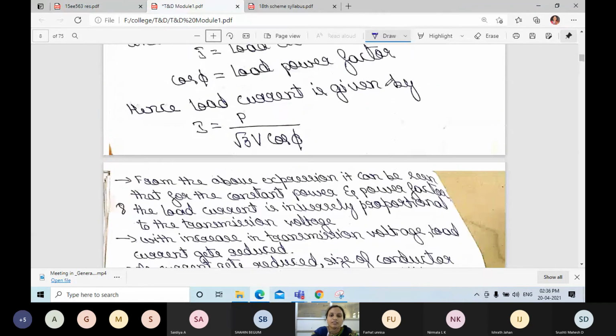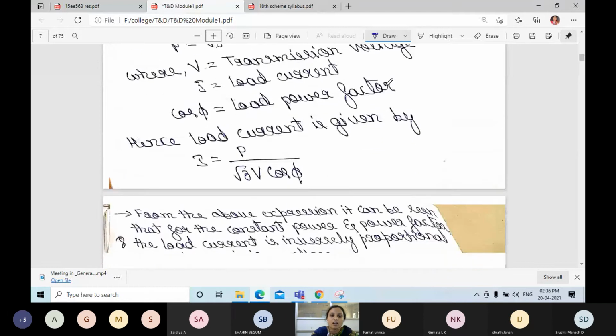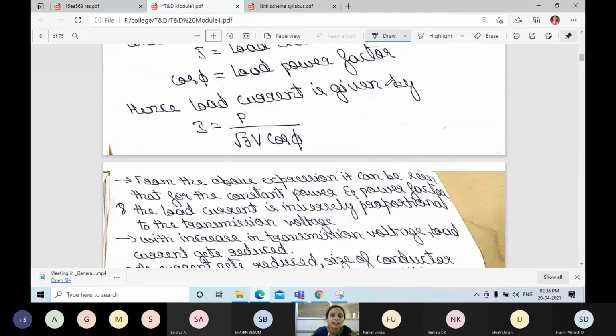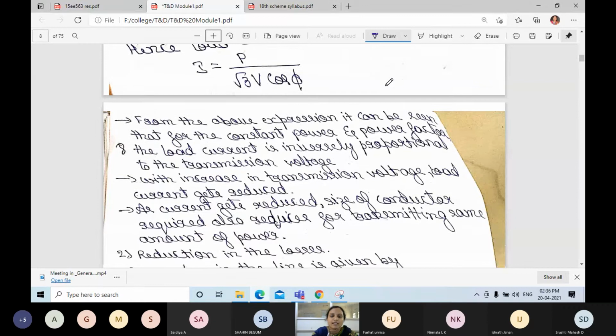What is the use of reducing current? From the above expression, it can be seen that for constant power and power factor, the load current is inversely proportional to the transmission voltage. If we increase the voltage level, the current automatically gets reduced. If the current gets reduced, then the size of the conductor required for transmitting the same amount of power also reduces, and the cost also reduces. This is the first advantage.